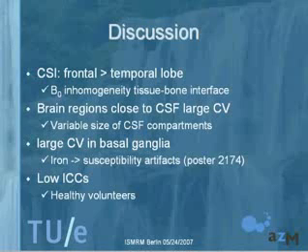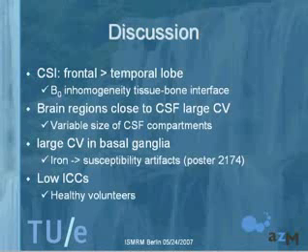The temporal lobe suffers from B0 inhomogeneity due to tissue-bone interfaces nearby. Furthermore, we noticed that brain regions close to CSF-containing spaces have large coefficients of variation, probably due to the variable size of CSF compartments throughout the population studied. We also noted large coefficients of variation in the basal ganglia, and we hypothesize this is related to iron. Iron induces susceptibility artifacts, and these artifacts are apparently not reproducible — at least with the methods we used — probably because of head positioning: if the head is slightly tilted relative to the first session, it induces large artifacts.